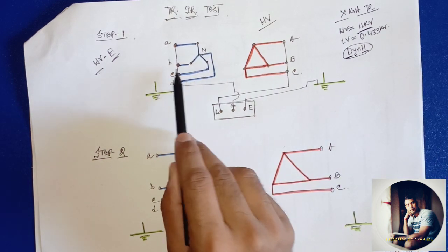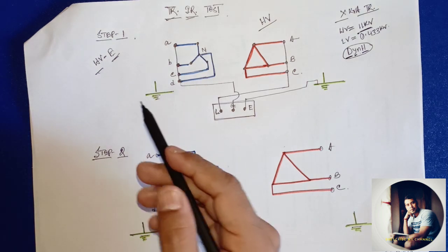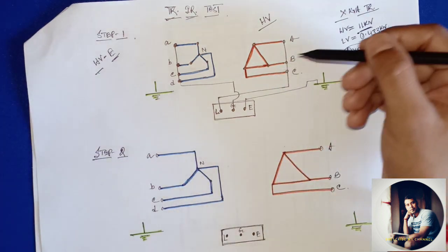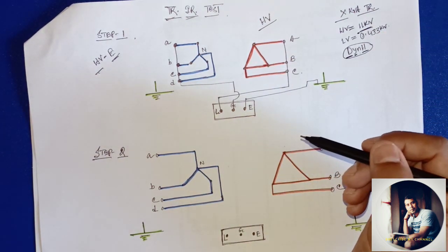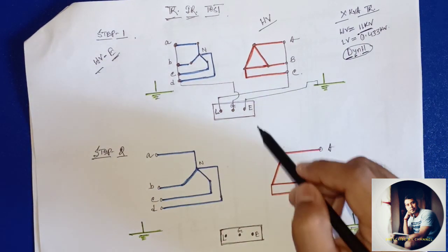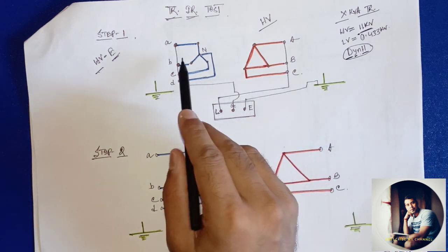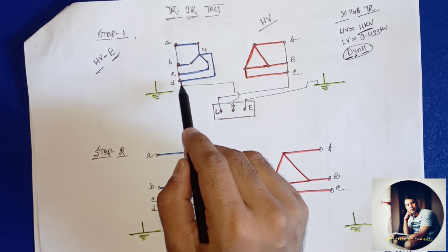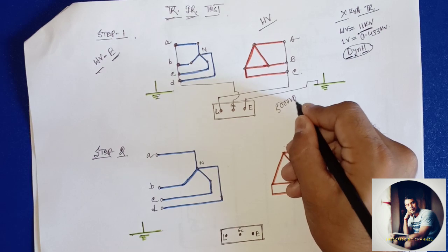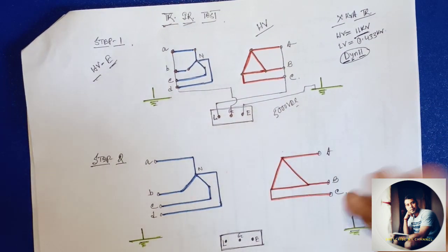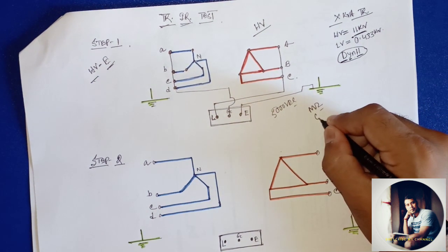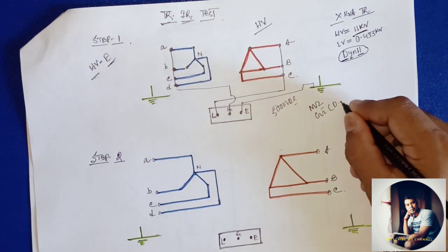So this part is connected with the guard, because we are not taking the test method, because there is not high voltage side right now. We are taking the IR test high voltage to earth. So the L terminal gets connected with ABC after shorting it, and the E terminal with earth, and the star points, all 4 points after shorting, connected to the guard. Then we can simply apply 5000 volt DC and we can get the result in mega ohm, giga ohm also in case of a digital megger.